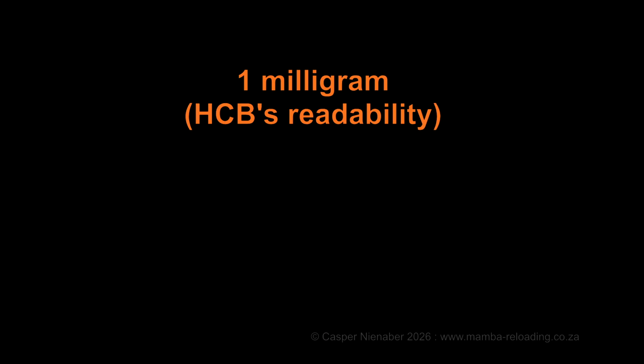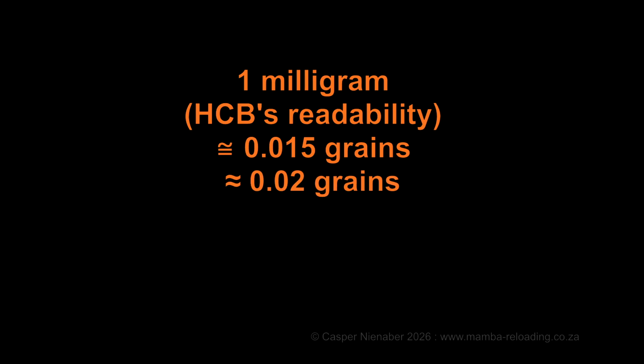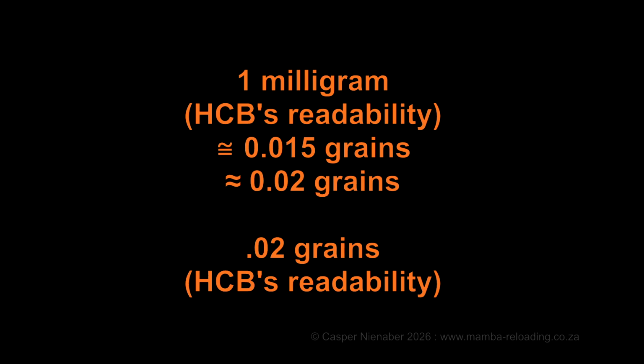Note that 1 milligram, which is the HCB's specified readability, is approximately equal to 0.015 grains and is rounded to 0.02 grains. This value also represents the HCB's readability in grains, meaning the balance displays measurements in increments of 0.02 grains.